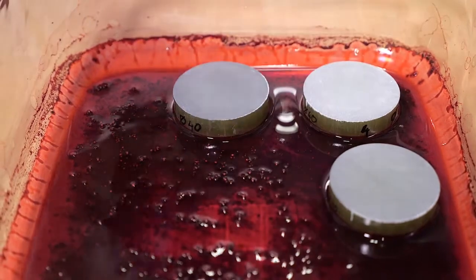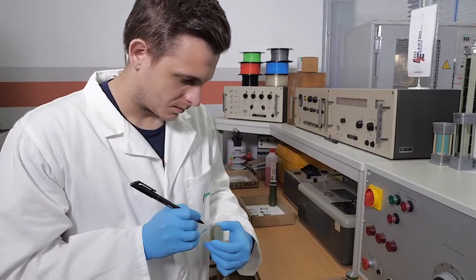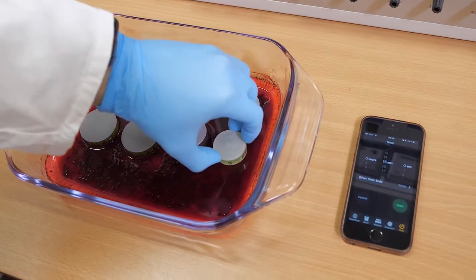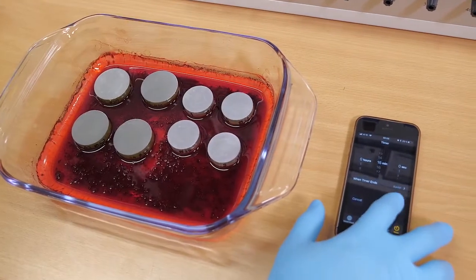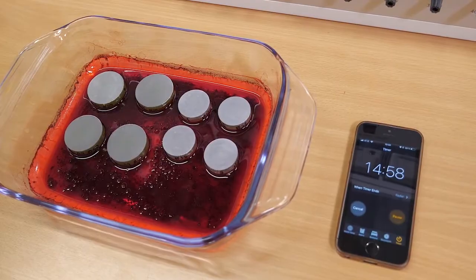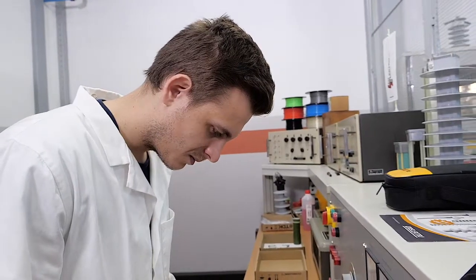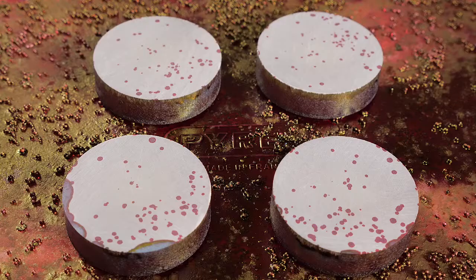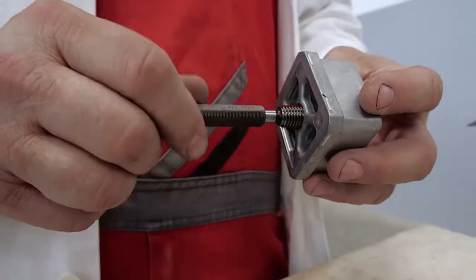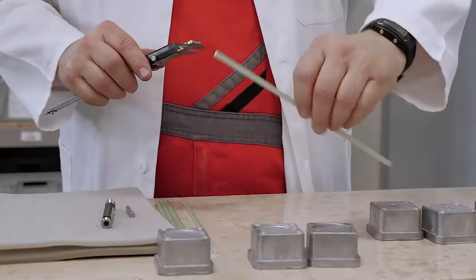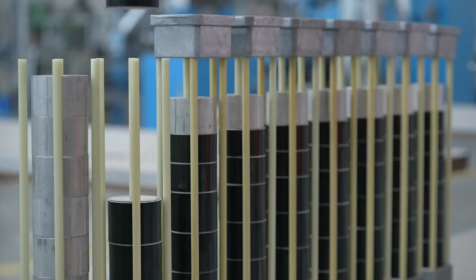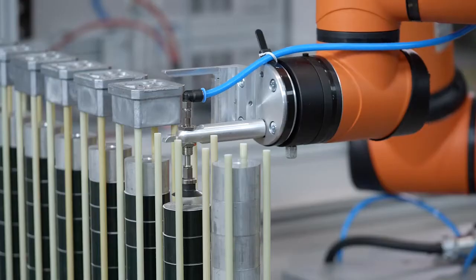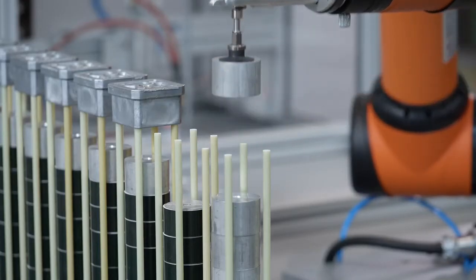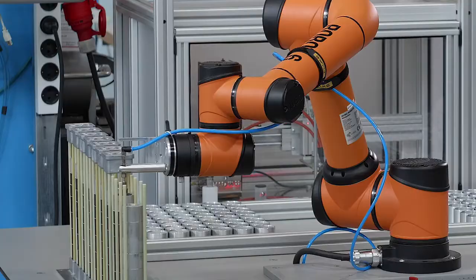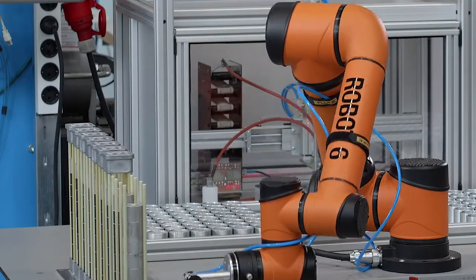Electrical corrosion-resistant epoxy rods in the core of the surge arresters are tested for moisture penetration according to the specified dye penetration test. In case the dye penetrates the top layer of the samples in 15 minutes, we reject the whole shipment. The rest of the components are checked using the sample method with calibrated measuring tools. The cores of the DH class surge arresters are assembled according to the continuous operating voltage and creepage distance specified by the buyer.